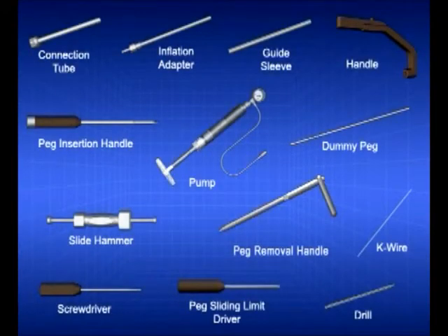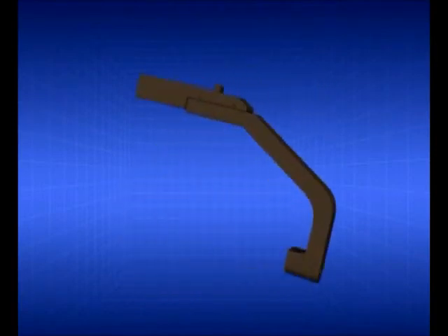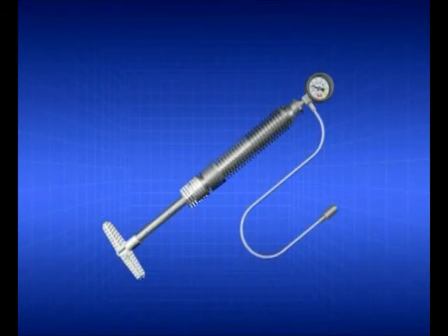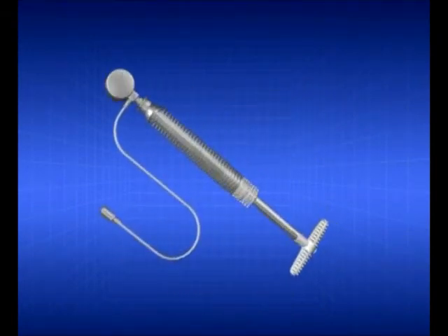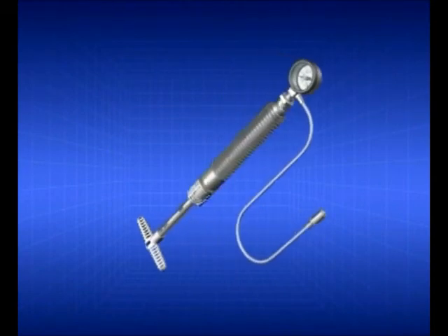The system accessories include an instrument set for insertion and removal of the implantable components and an inflation device. The nail insertion handle through which the peg is introduced is radiolucent. The pump is designed to deliver saline to the nail and to the peg in order to expand them. The pressure gauge on the pump allows controlled inflation.